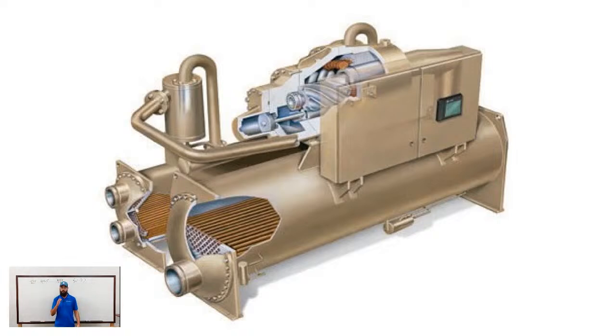So if our set point is 45 and we get to 46 degrees and stay above 46 degrees for 30 minutes, that's when the system would start looking at bringing in the lag chiller and having it come alongside and help out. Now they can be more responsive than that. That really just depends on the system, but that's pretty common.